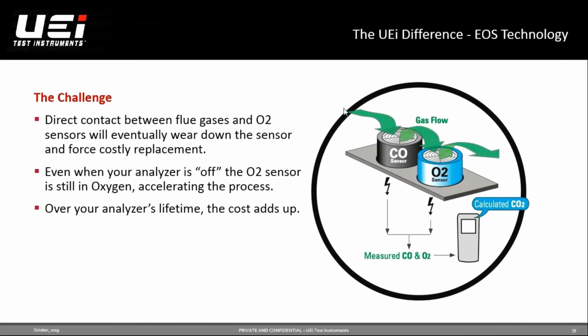There's a challenge because a traditional combustion analyzer is going to have oxygen and CO sensors. What are we breathing in the air? We're breathing oxygen. So if you have a sensor that's designed to breathe oxygen, it's going to constantly be breathing oxygen, and that becomes a problem, because how do you know when that sensor is going to die? You don't know how long ago that O2 sensor was manufactured, how long it sat in a warehouse or on a shelf. Or maybe you've put it away for the season, and it's highly possible you'll wind up with an O2 sensor that has died. And I don't know if you've priced out the cost of oxygen sensors, but they add up pretty quickly for something whose lifetime even our best guesses can be wrong about.